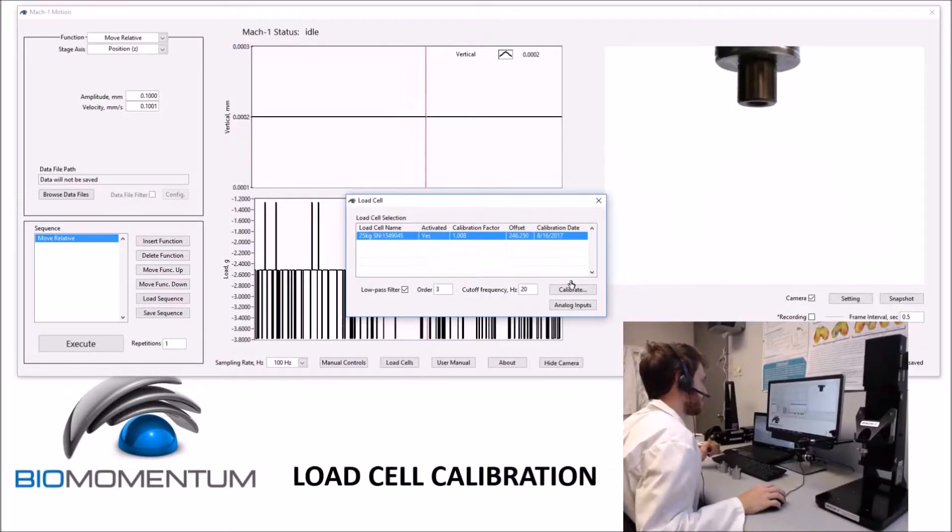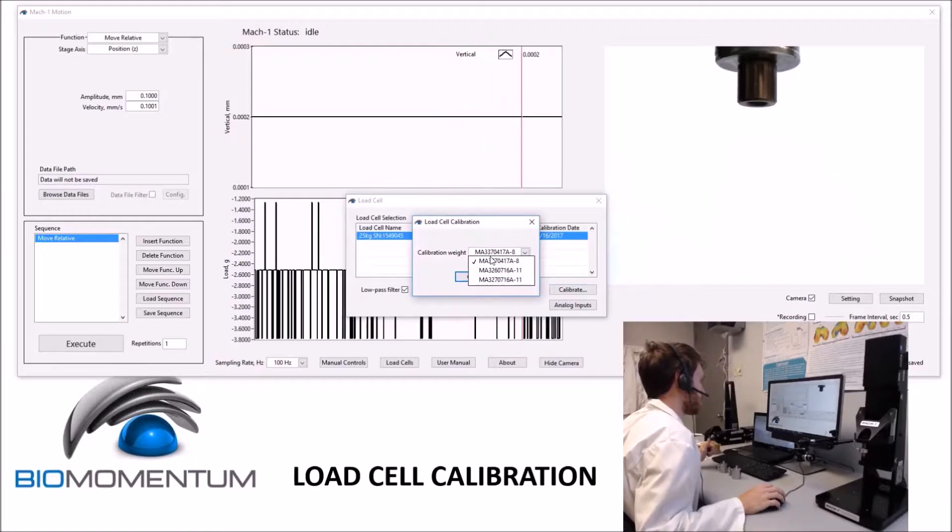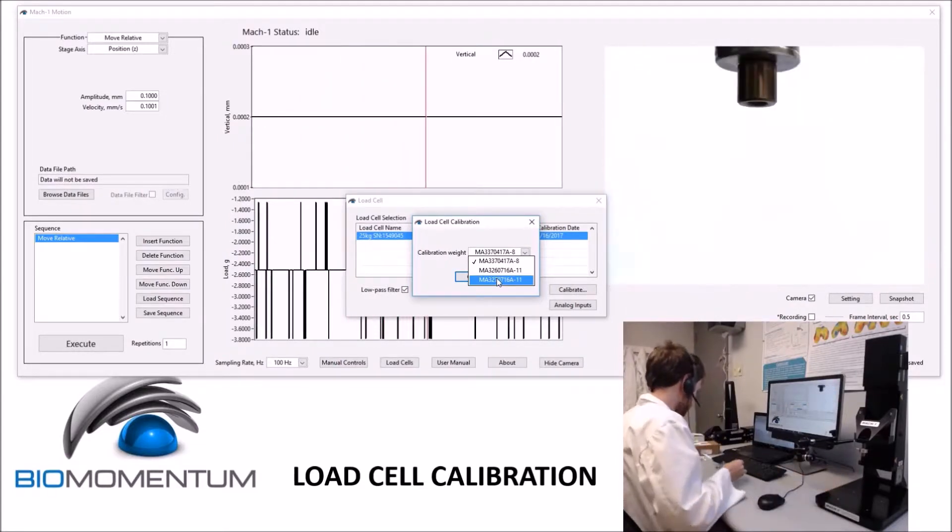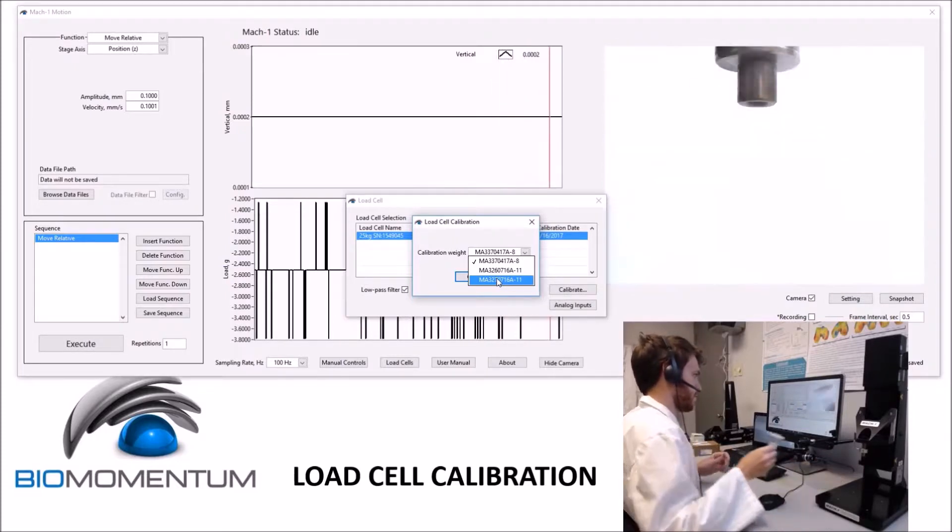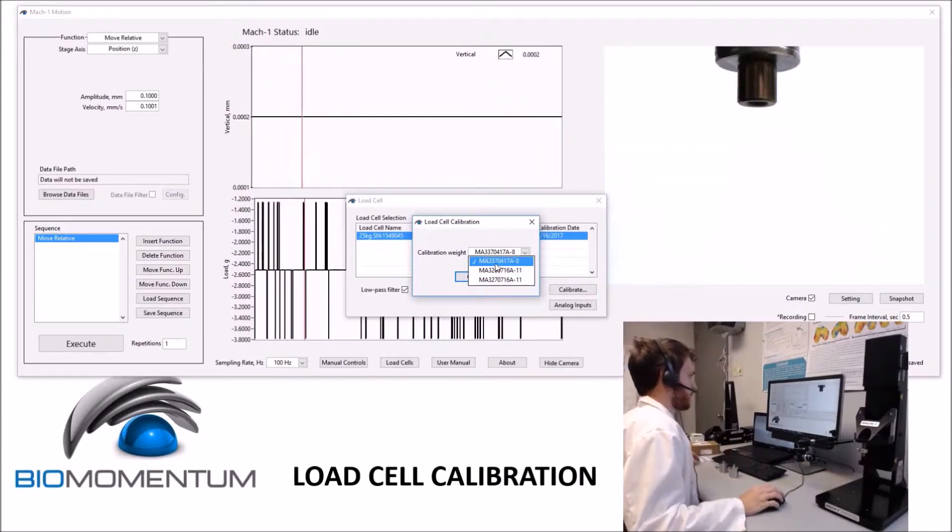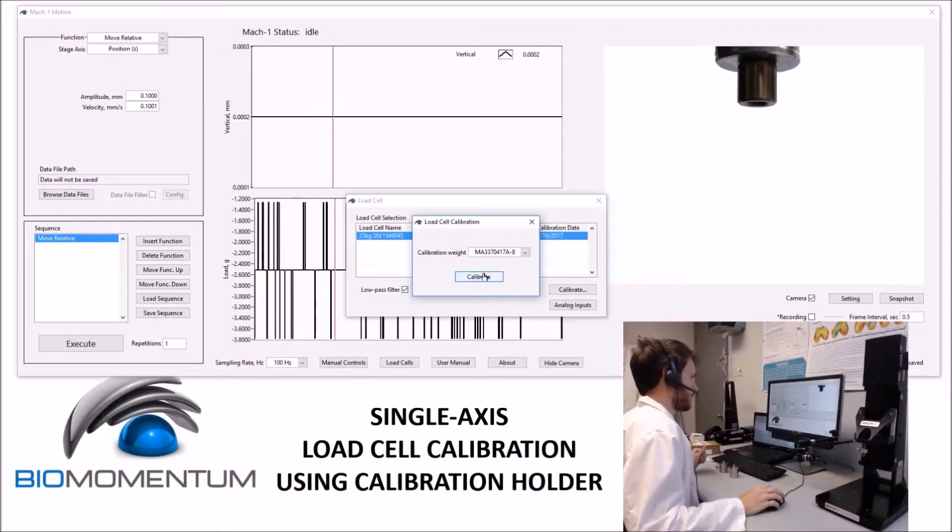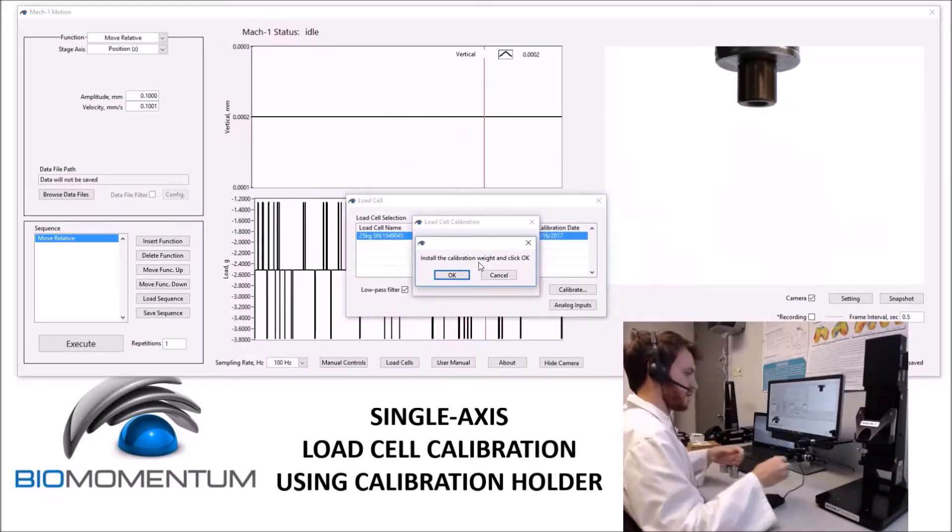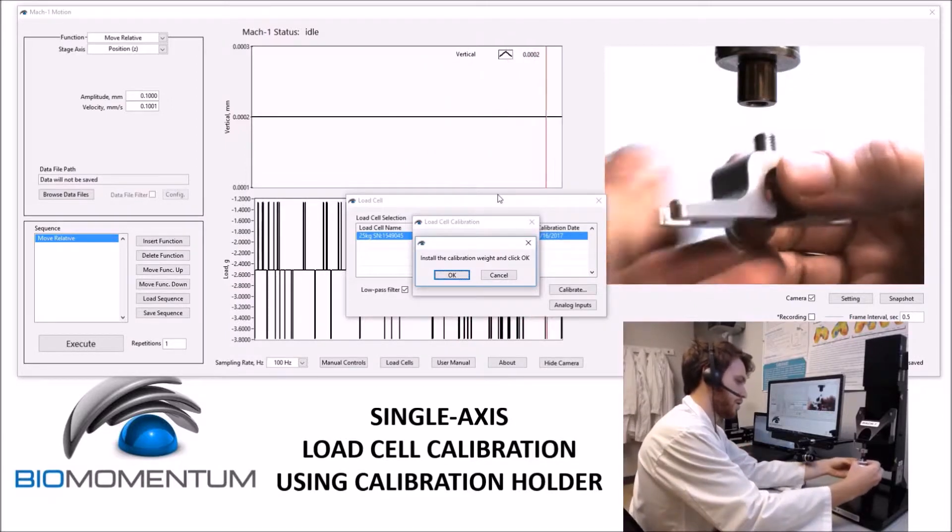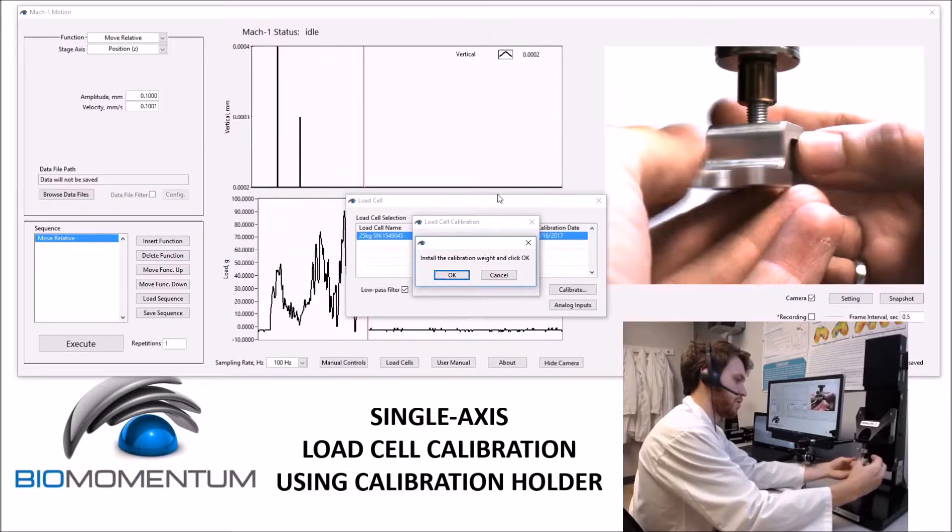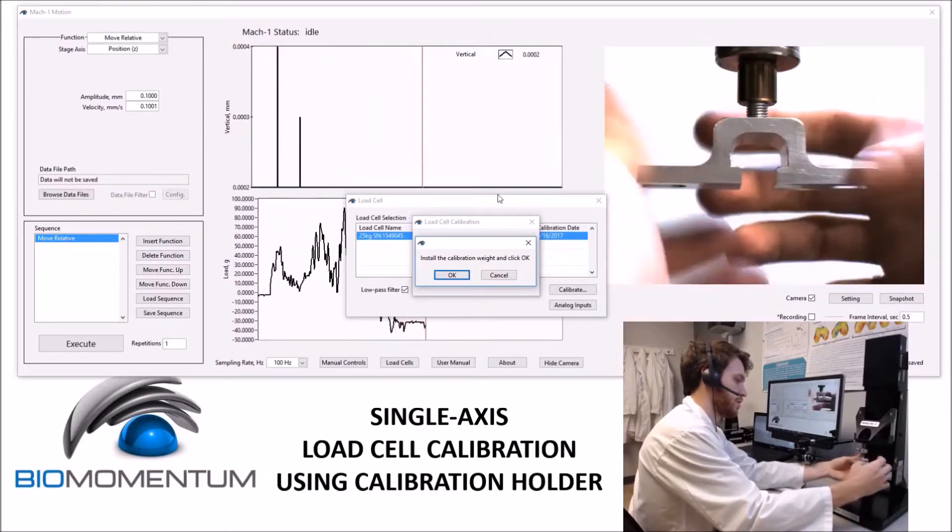To calibrate a load cell, click the Calibrate button. This will open a new window where a calibration weight can be selected from a drop-down list. The names of these calibration weights are usually written on the weight themselves, or on the bag that the weight came in. For this method, I will click the Calibrate button, and then follow the instructions on screen. I will first install the calibration holder, being careful not to overload the load cell.